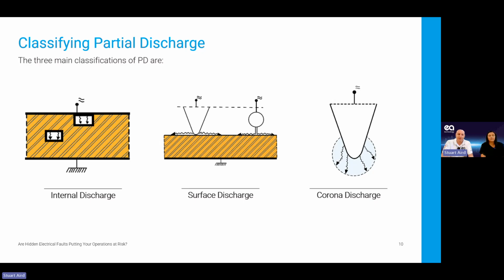So for that type of partial discharge, the primary way of detecting it, or the only real easy way, is to detect it through transient earth voltages. So we pick those up with our sensor, a capacitive coupler on the outside, or things like HFCTs or UHF type sensors as well. So they're for the internal partial discharges.